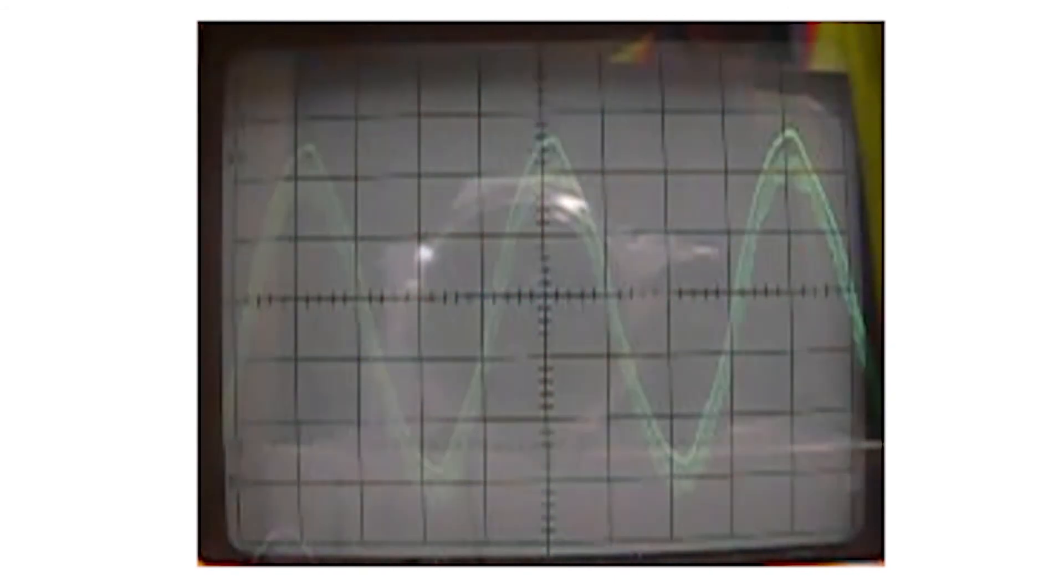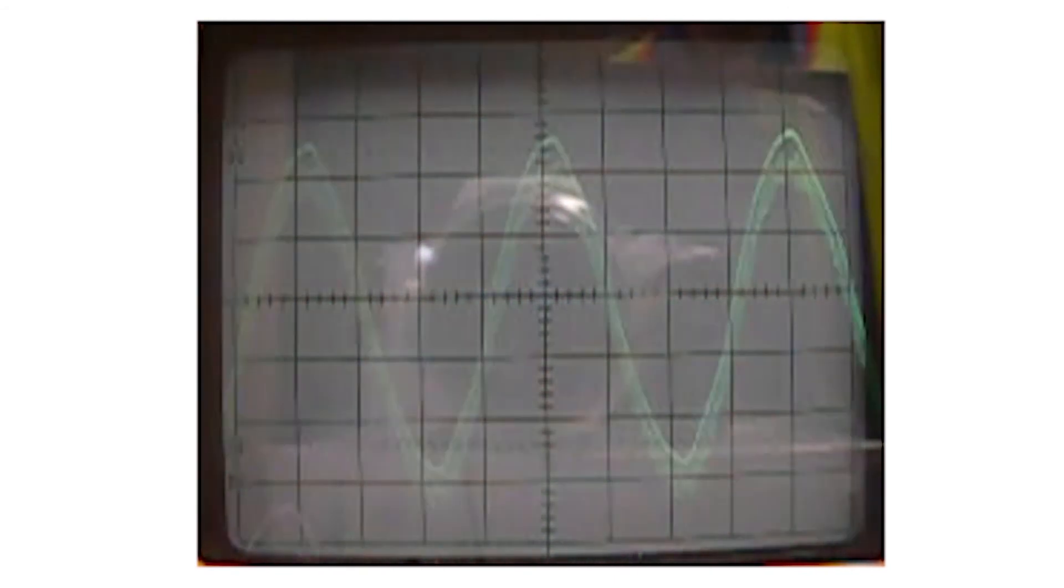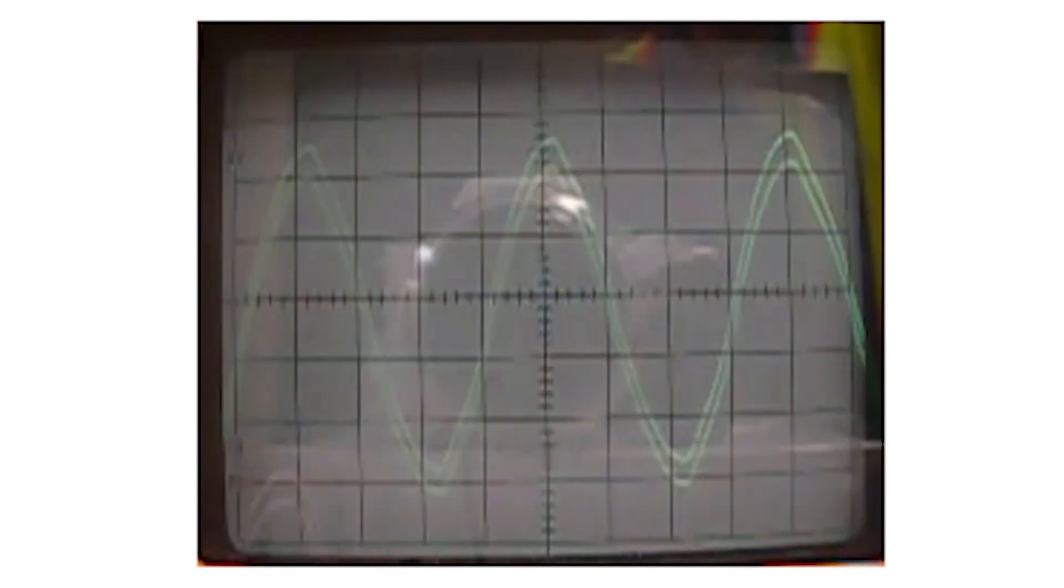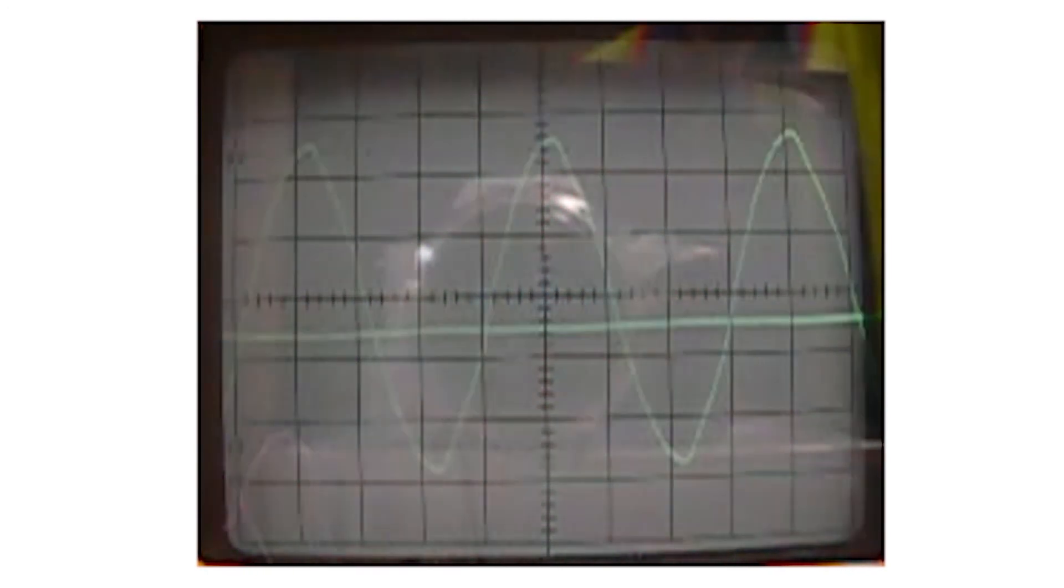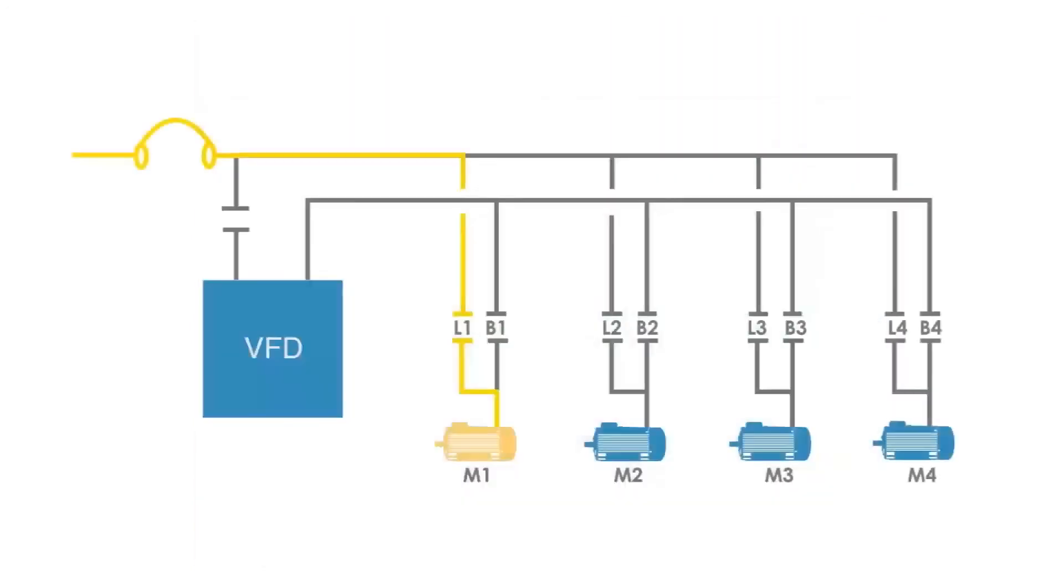Once the drive output and the line are within 1.5 degrees of phase with each other, the VFD will transfer the motor to the line and the VFD will be commanded off. The motor has been transferred from the VFD to the line.